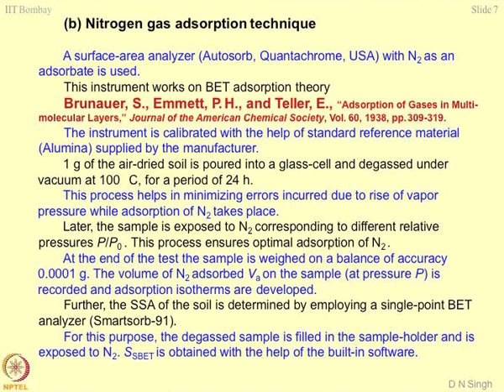The sample is degassed at 100 degrees centigrade for a period of 24 hours. Degassing is nothing but removing all the vapours associated with the sample, so that the nitrogen gas gets a better chance to get adsorbed on the surface of the particles. This process helps in minimizing errors due to rise of vapour pressure while adsorption of nitrogen takes place.